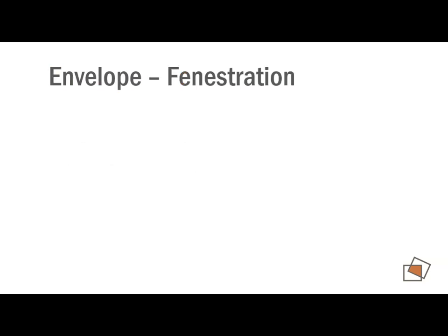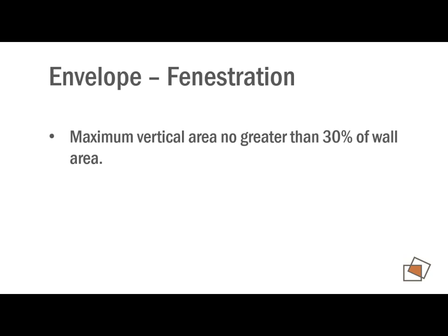So looking next at fenestration, there's a few requirements right off the bat. This may have an influence on your design. It's a constraint. It says that your maximum vertical fenestration area can be no more than 30% of your wall. So they're dictating to you right off the bat how many windows you can have in your building. That could be something that kicks you right into a performance compliance method if your design can't adhere to this.